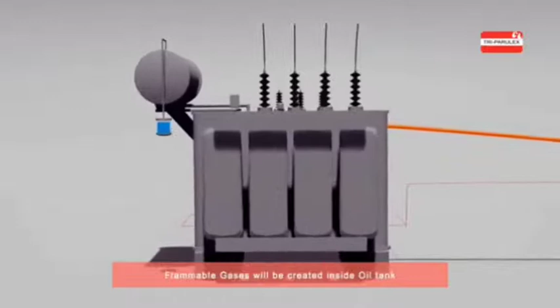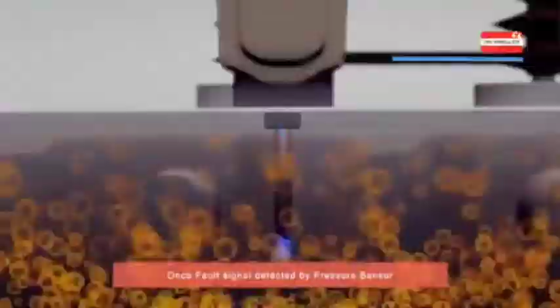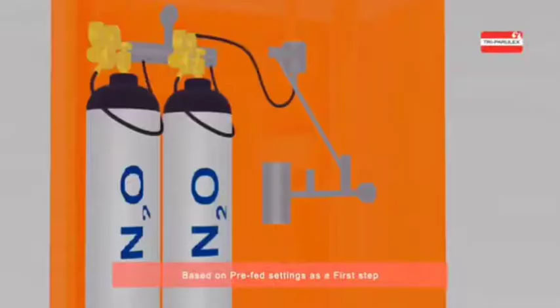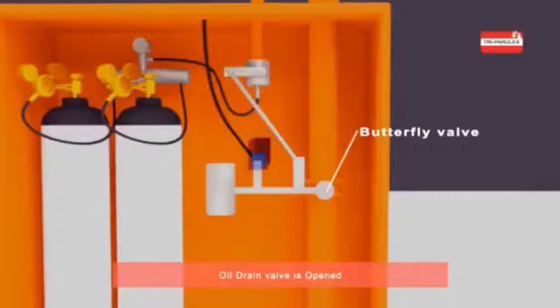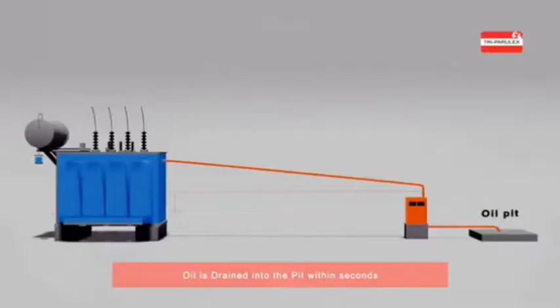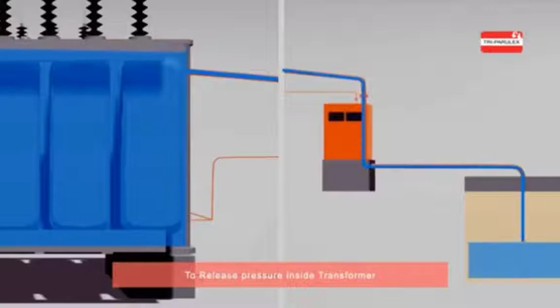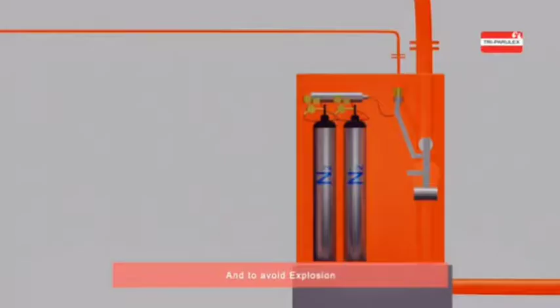If the transformer is not working properly, an enormous amount of flammable gases will be created inside the oil tank. At this moment, the internal pressure of the tank increases due to thermal inertia. Once a fault signal is detected by the pressure sensor, the signal is sent to the control room. Based on the pre-fed settings, as a first step, the oil drain valve is opened and the oil is drained into the pit within seconds after detection in order to release the pressure inside the transformer and to avoid explosion.